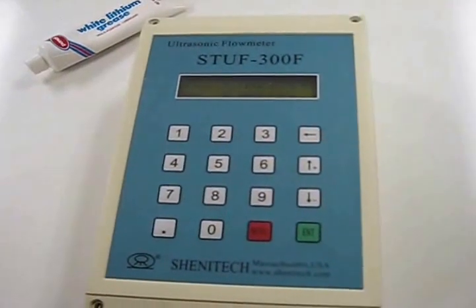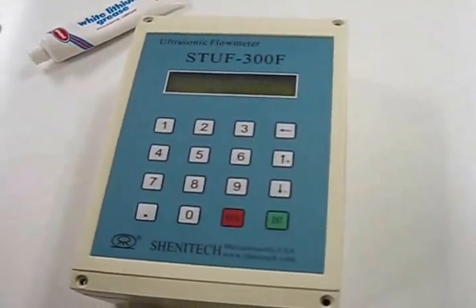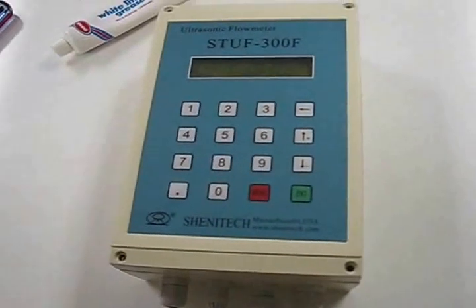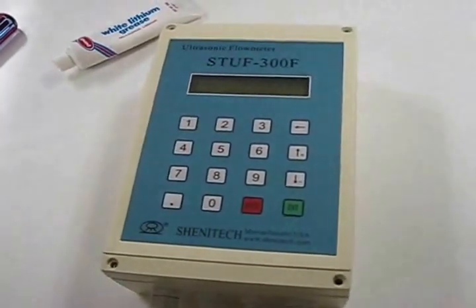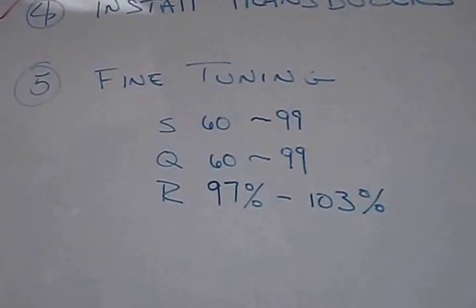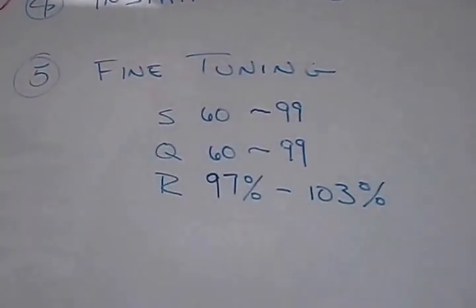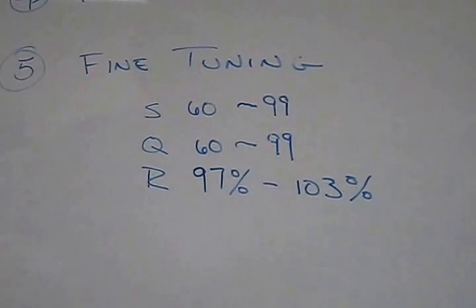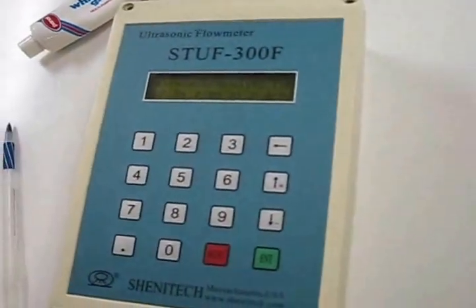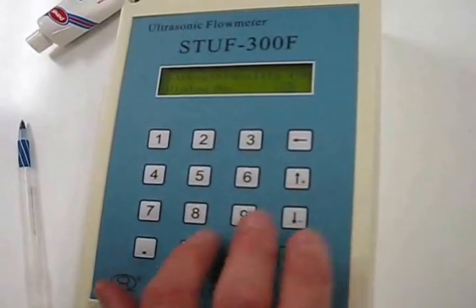The purpose of the fine-tuning process is to ensure our transducers are installed properly and the flow meter is configured correctly. There are 3 parameters we need to check. Signal strength, signal quality, both should be above 60, and the transit time ratio should be between 97 and 103%. Let's go to our flow meter and check our numbers. We go to menu 90.